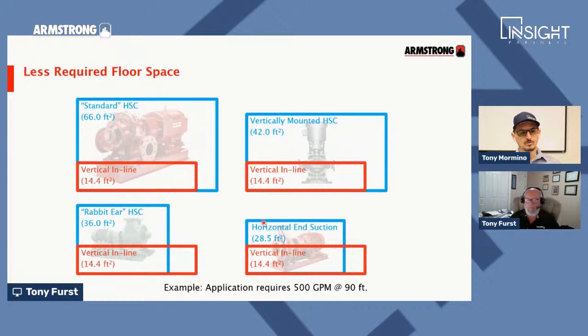Tony, does that hold true for the larger horsepowers? And what's the biggest horsepower vertical inline pump you can get? Armstrong makes vertical inlines up to 1,250 horsepower. That's a big one. Yes. And all of those pumps are designed to be 100% supported from the piping system. They don't require any additional supports underneath the pump. It's 100% supported by the piping system.